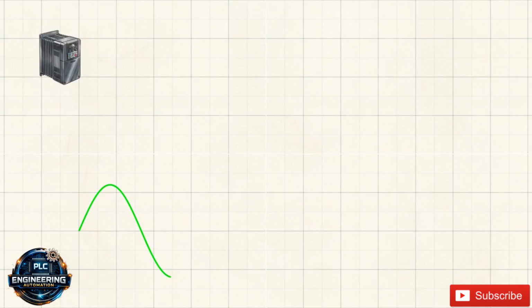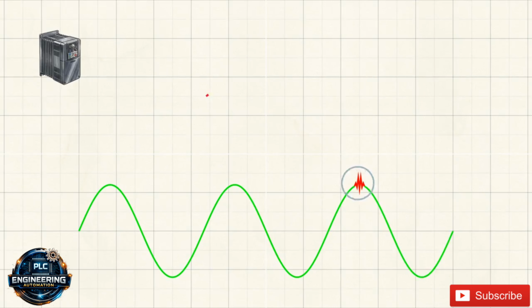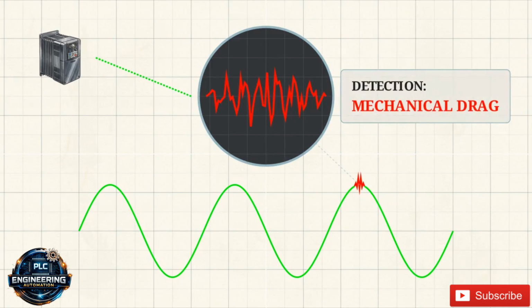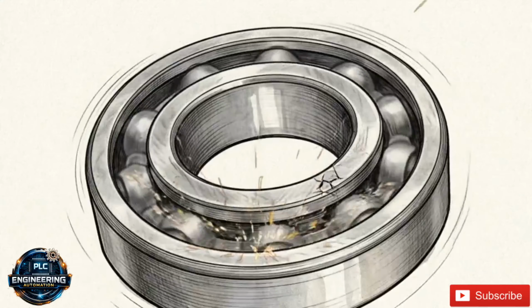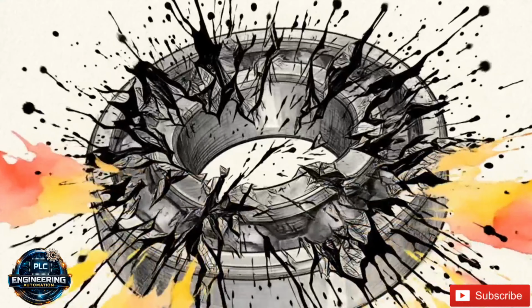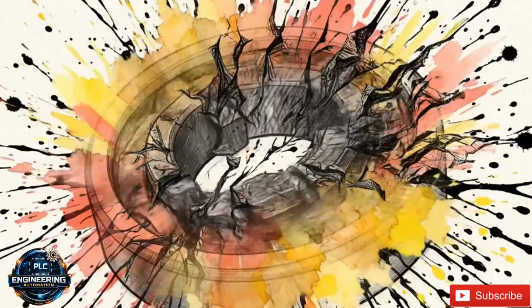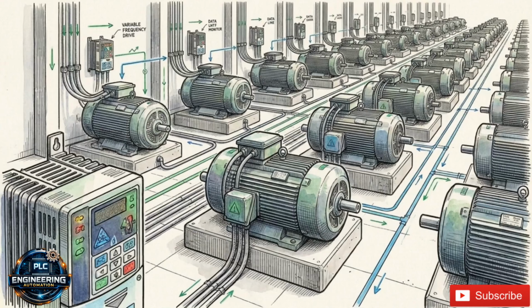We are already seeing modern drives analyze their own output current waveforms to detect tiny mechanical drag forces. They can identify the specific electrical signature of a degrading motor bearing weeks before the physical breakdown occurs. This constant micro-level analysis transforms the VFD into the most powerful predictive maintenance tool on the industrial floor.